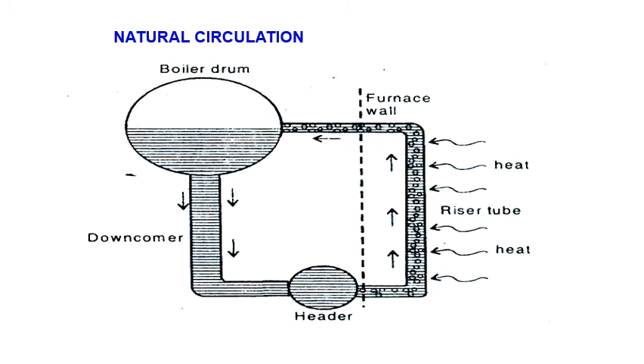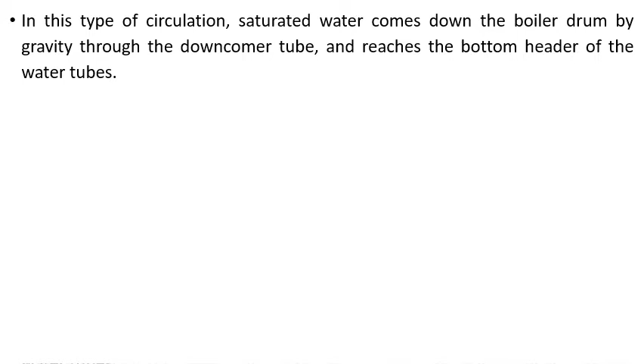From there, because of density difference, it will occupy the upper space of the drum, and the water which is still in water form will be entering into the furnace. So in this type of circulation, saturated water comes down from the boiler drum by gravity, through the downcomer, right? So there is no need of any forced circulation pump.